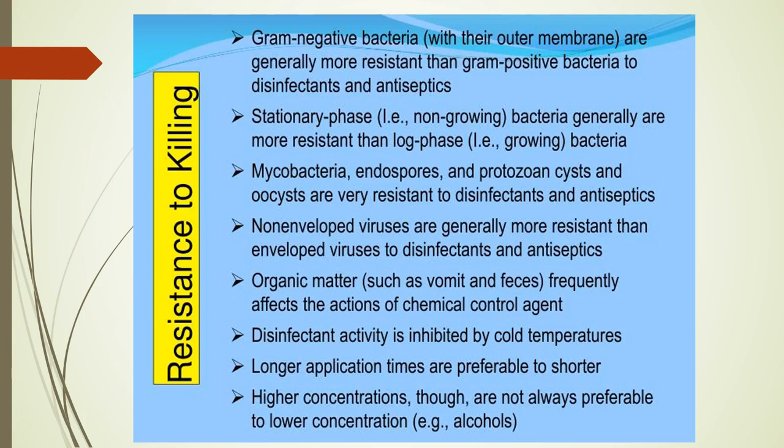Probably the most important issue is cleaning the instrumentation of organic matter, because organic matter will interfere with the effectiveness of a disinfectant in several manners. You may have actual biochemical or physical interaction between the disinfectant and the organic matter, so that by the time the disinfectant reaches the surface of the object to be disinfected, it is no longer going to be effective. And you also have just the physical blocking, the lack of access of the disinfectant to the surface of the material because of dried pus or dried blood or whatever.